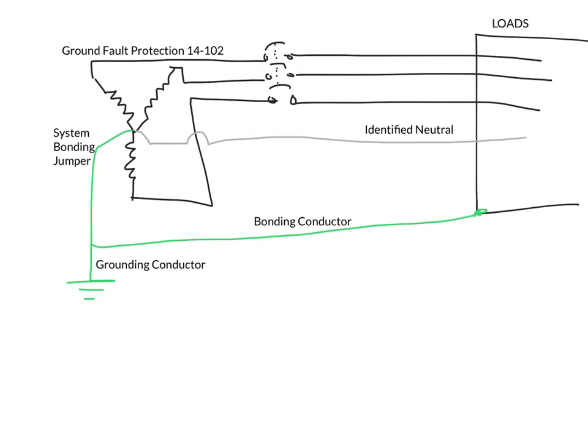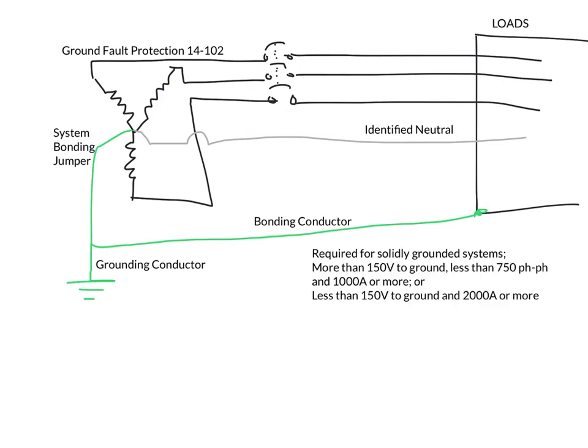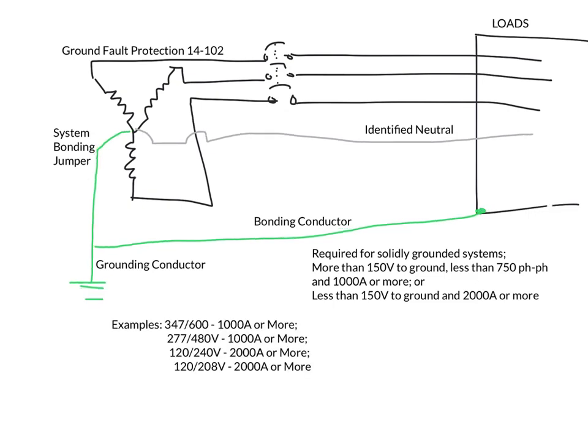So when you're looking at the requirements for this rule, you'll see that it talks about systems that are solidly grounded, rated more than 150 volts to ground, less than 750 volts phase to phase, and 1,000 amps or more, or for circuits that are solidly grounded, rated 150 volts or less to ground, and 2,000 amps or more. So a few examples of these types of circuits would be a 347/600 volt circuit at 1,000 amps or more, or 277/480 volts at 1,000 amps or more.